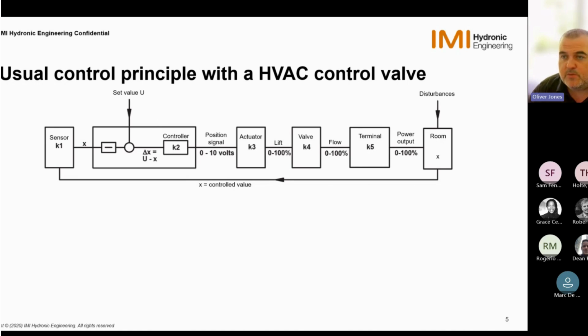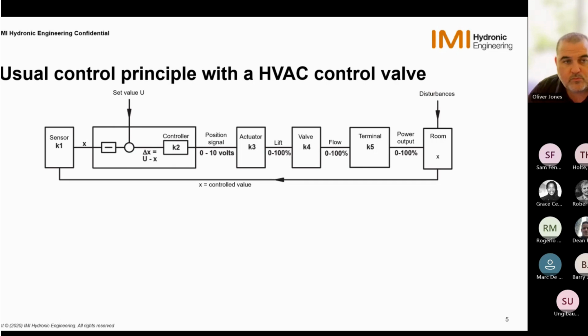So the sensor sees the current temperature, which is our X value, and that's taken as an input by our controller. The controller takes the set point value, which is U, which we can see here, and calculates the deviation between the set point U and the measured temperature value X. Based on this deviation, the controller will apply a certain gain, which is shown as our K2 in the controller. And this is used to calculate a position signal, which we can see here, out of the controller.